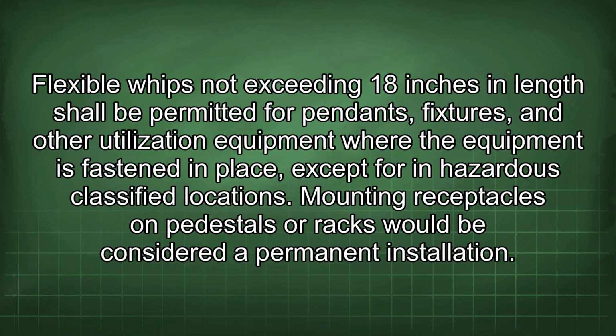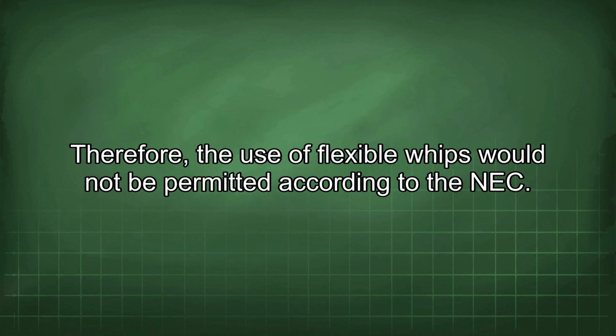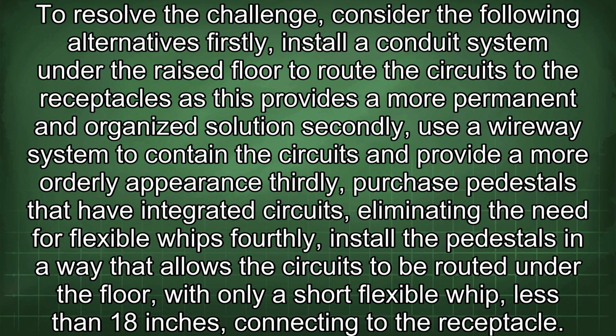Mounting receptacles on pedestals or racks would be considered a permanent installation. Therefore, the use of flexible whips would not be permitted according to the NEC. To resolve the challenge, consider the following alternatives. Firstly, install a conduit system under the raised floor to route the circuits to the receptacles, as this provides a more permanent and organized solution.